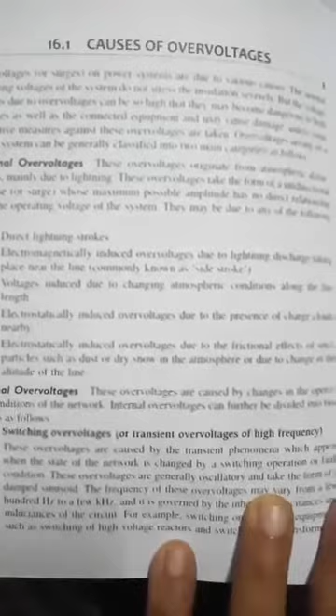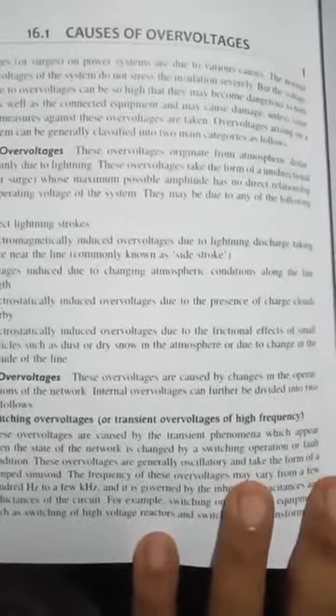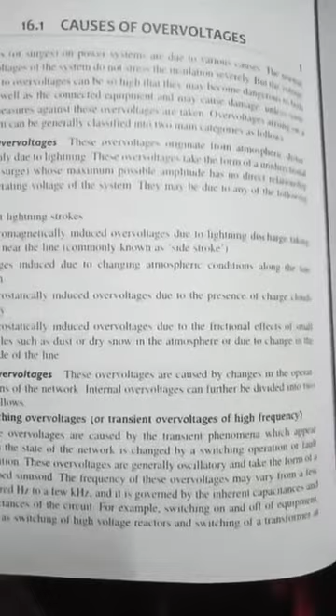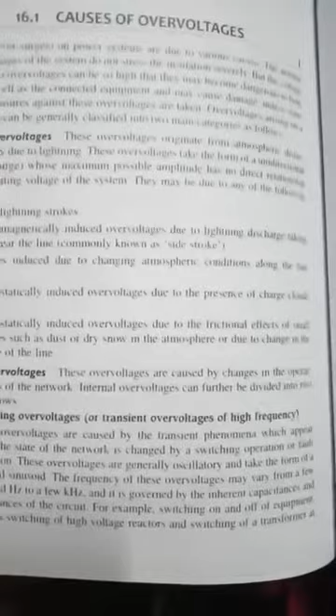Next question, what are the causes and effects of over voltages? Over voltages on power systems are due to various reasons. Normal operating voltage of the system does not stress the insulation severely, but the voltage stresses due to over voltages can be so high that they may become dangerous to both the line as well as the connected equipment and will cause damage unless some protective measures against these over voltages are taken. So over voltages arising on a power system can generally be classified into two categories: external over voltages and internal over voltages.